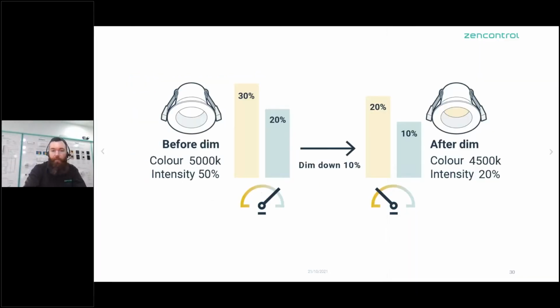The other thing that was tough was actually dimming them, because inherently, as you dim to different levels, you're going to get an offset on the color, right? So one of the big problems was that whilst you could generate this sequence that moved from a warmer to a cooler color over a range of intensities, if you wanted to put a button to temporarily dim the lights up and down or adjust the color temperature, that was hard. And we'll look at one of those examples here.